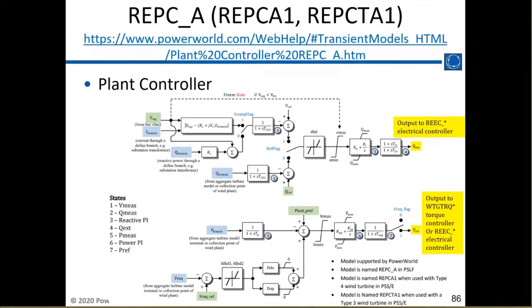All of these models are looking local—they're looking at the local control of the wind turbine. This is the plant controller, the one looking out at the point of interconnection. So this is where you have to say, I am regulating at the plant level. Let's say it's regulating this bus, and I am regulating the power flowing in here, and the reactive power, and also current matters here too. So as part of the input parameters for this model, you have to give it a branch and a voltage bus, one of the terminals of the branch, where the plant is measuring voltage and power, and then has to be sending that data back via telemetry to all of the individual wind turbines. So this is what the REPCA is looking at out there.